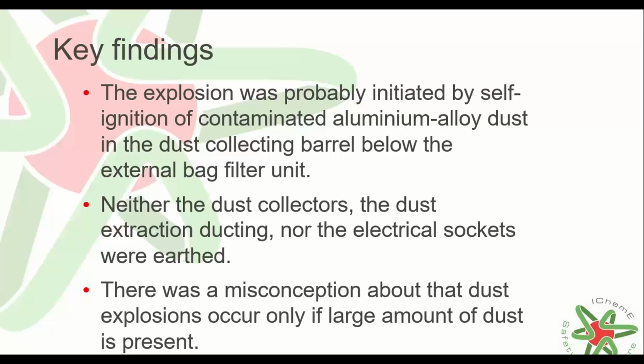At the same time, neither the dust collectors, the dust extraction ducting, nor the electrical sockets were earthed. So in comparison to the previous case, in this particular company, there was no such good housekeeping procedure in place. They were not aware of the importance of earthing such equipment, so that knowledge was not available.